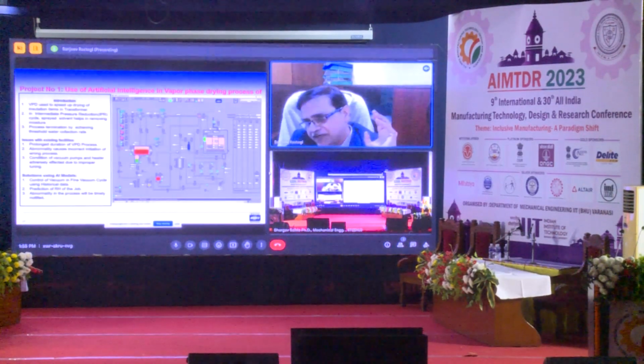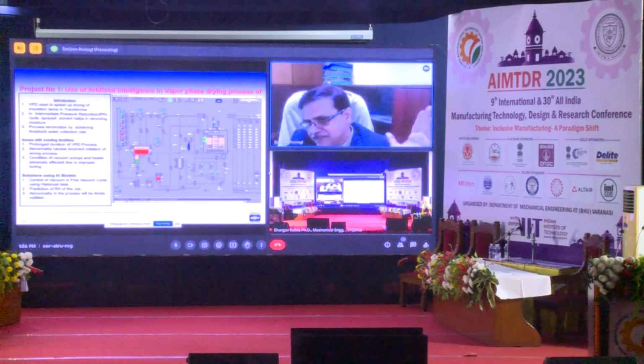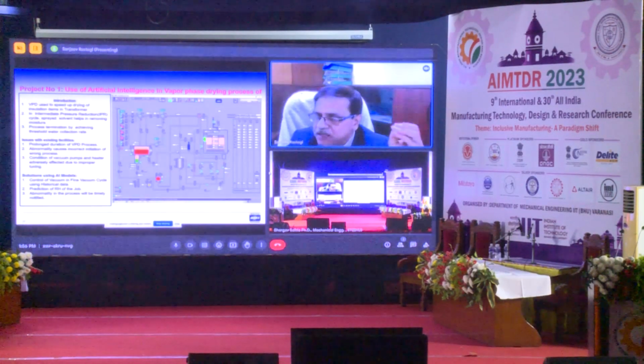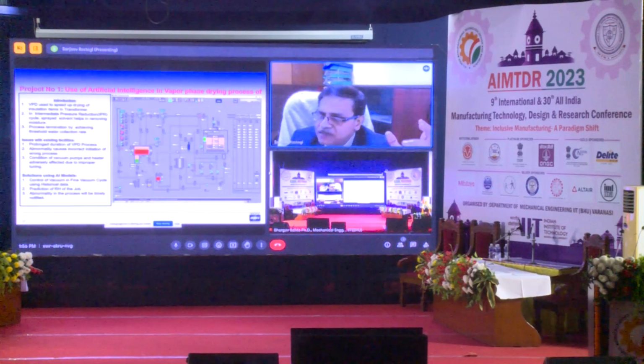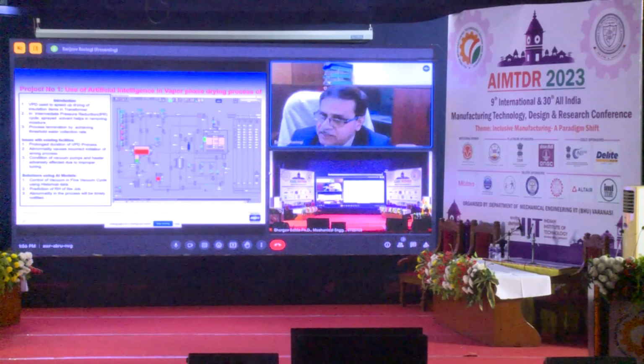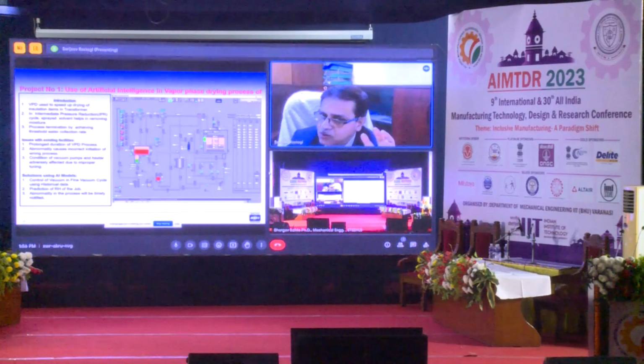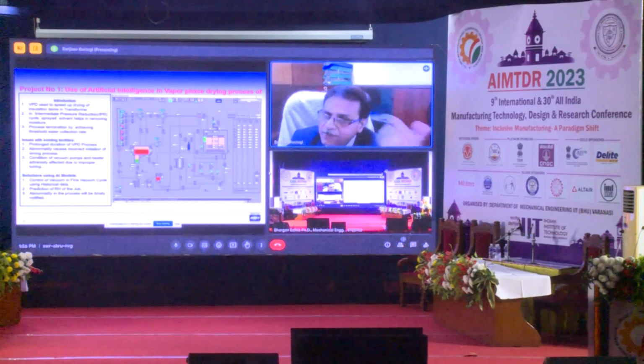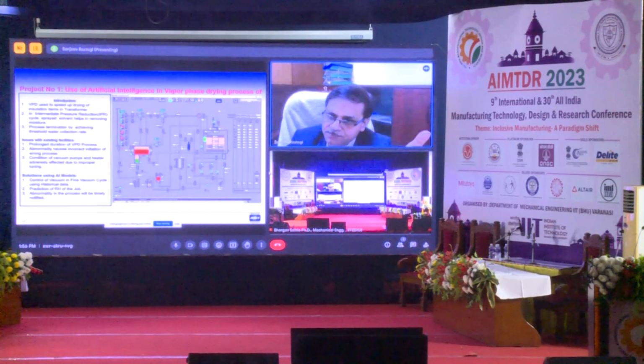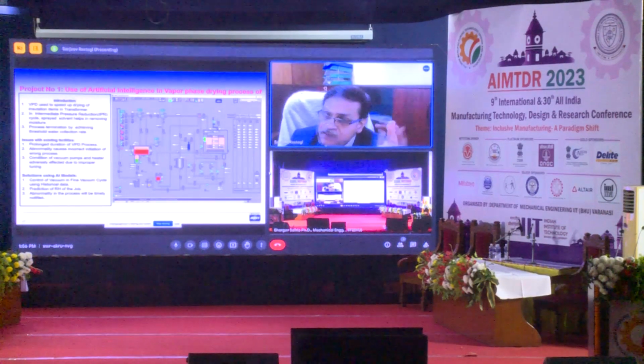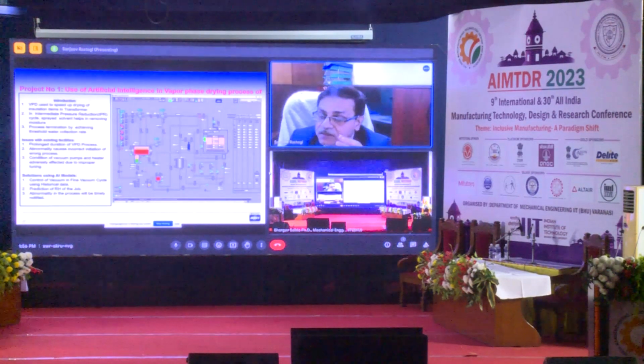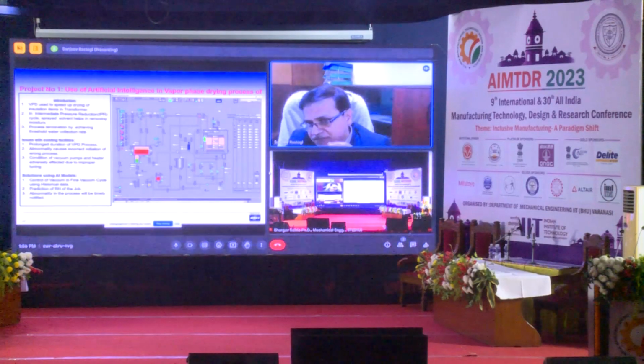Similarly, we have drawn a digital twin of our VPD vessels, vapor phase drying vessels, used for power transformer manufacturing. We have been able to predict the moisture and humidity in the transformer and thereby predict the cycle time of the job, which got delayed. This has also enabled a drastic reduction in fault levels of the transformers.